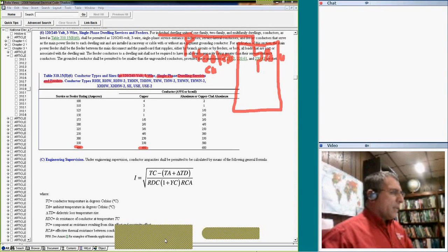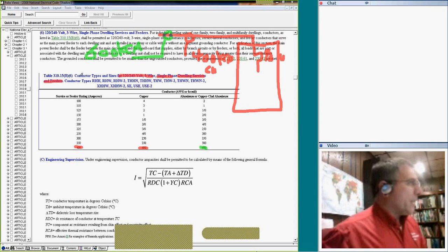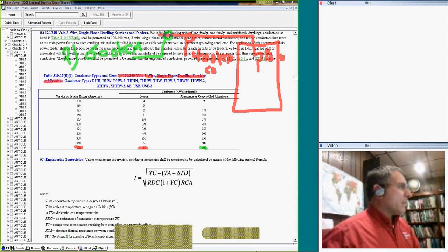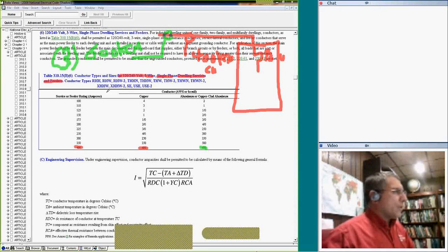So my friend, somebody else decided to go, okay, well, Chad, I'm going to use aluminum. I don't care about copper, I'm going to use aluminum. So if you use aluminum, then you're going to have 600 kcm. So that will be your two hots, basically. Your neutral, either you go the full neutral and make them 3, or you can go 1-2 steps below, or you do the neutral calculation.